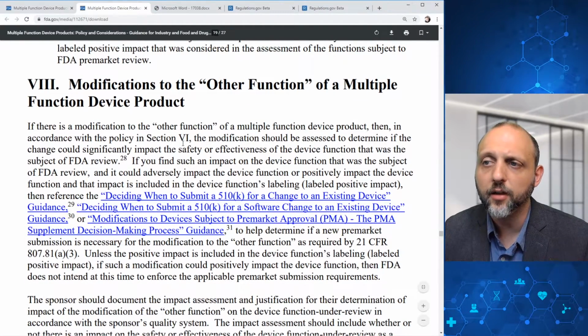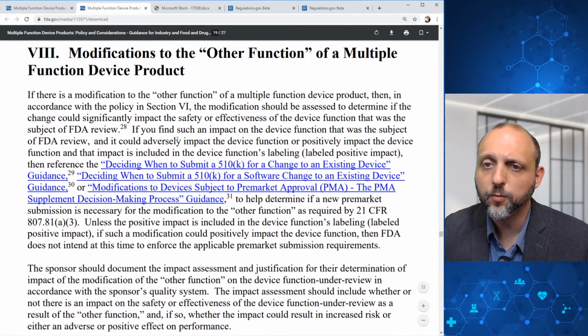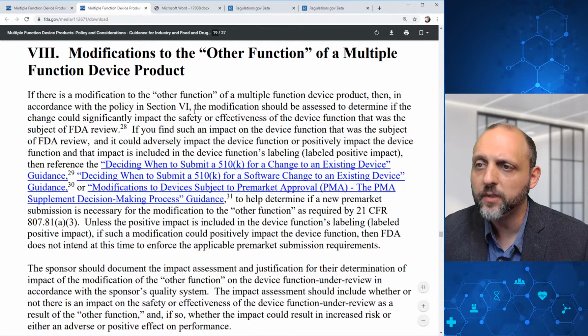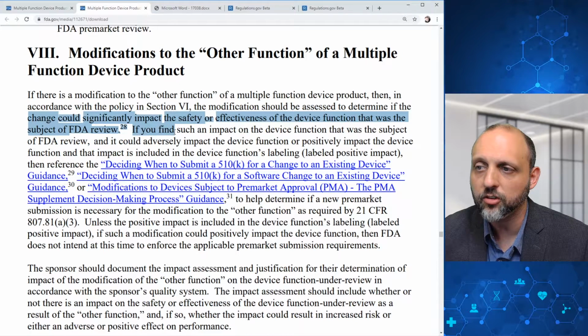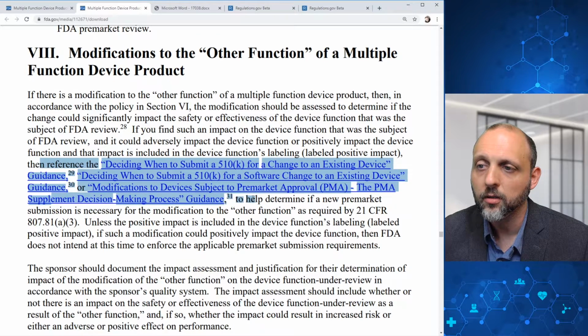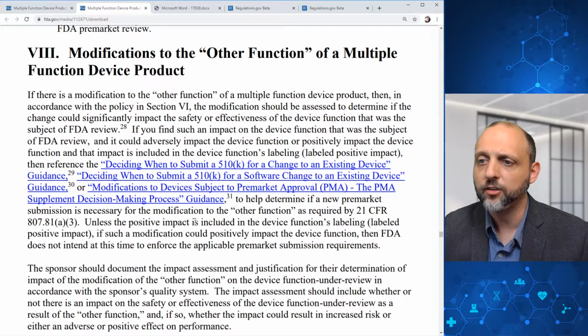And here, modifications to the other functions of a multiple function device product. If there's a modification, then in accordance with the policy set out above, the modification should be assessed to determine if the change could significantly impact the safety or effectiveness of the device function that was the subject of FDA review. If you find such an impact, and it could adversely impact the device function or positively impact the device function, and the impact is included in the device function's labeling, a labeled positive impact, then you need to reference Deciding When to Submit a 510(k) for a Software Change, or modifications to devices subject to PMA, pre-market approval, to determine if a new pre-market submission is necessary for the modifications to the other function.